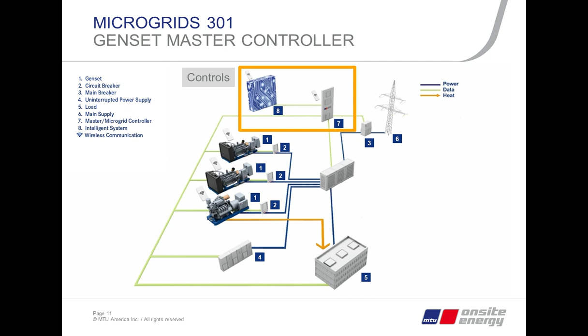Typical master control functions, as we see in this list, are really a high-level controller interfacing to the individual genset controllers for a multi-unit installation. It's controlling those different generators, having the start-stop sequence and power set points on each genset according to power or heat requirements if you have a CHP application. We'll want to load share between gensets, maybe level engine run hours across them so they're all at the same run hour. We'll synchronize and control breakers through the master controller. There's island operation logic for transitioning from grid parallel to island and back. There's visualization showing the breakers and gensets, and typically today we also have remote access. So it's really just the control of those assets.